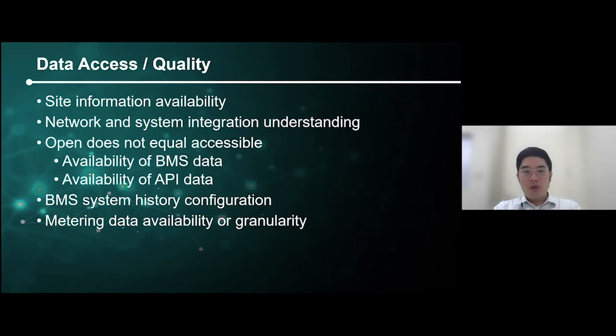While in a normal time series system we'd expect fixed time durations for data points, some BMS systems are configured using change of value instead. For normal operation that's not a big issue, but it creates additional uncertainty, since we wouldn't know if the BMS lost comms with that point, which is why we stopped getting data, or whether the data point just hasn't moved.